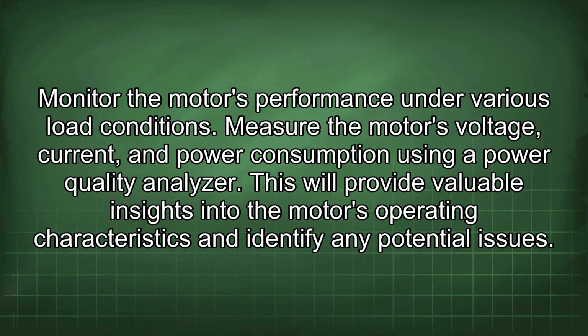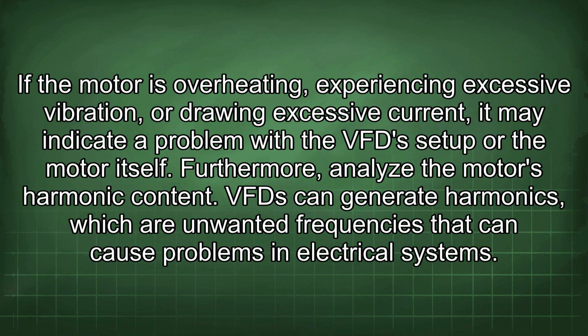Monitor the motor's performance under various load conditions. Measure the motor's voltage, current, and power consumption using a power quality analyzer. This will provide valuable insights into the motor's operating characteristics and identify any potential issues. If the motor is overheating, experiencing excessive vibration, or drawing excessive current, it may indicate a problem with the VFD setup or the motor itself.